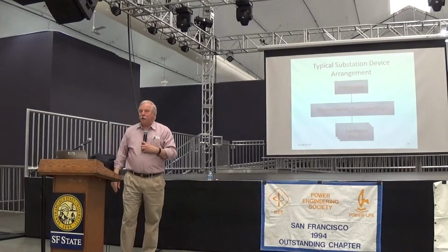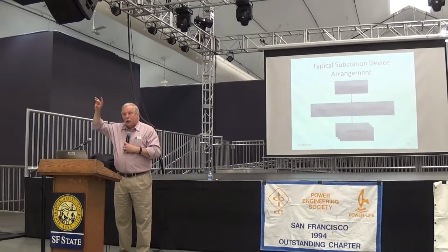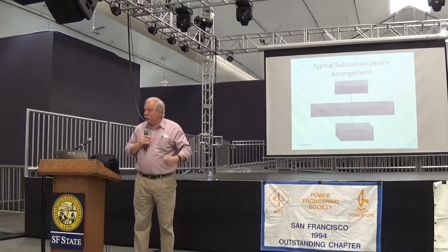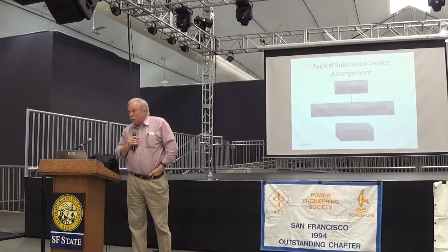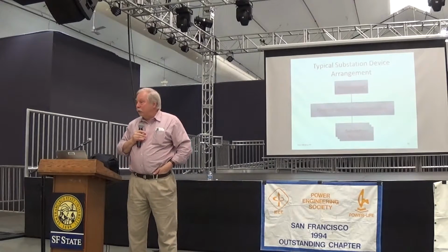So in a substation, we have an architecture that looks like a grandmaster, an Ethernet switch, and then many, many substation devices connected to the Ethernet switch. The goal here is that all the substation devices are synchronized to the same grandmaster clock.